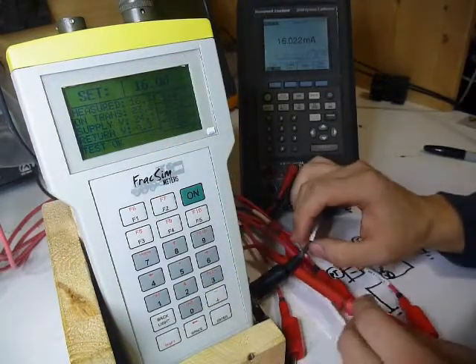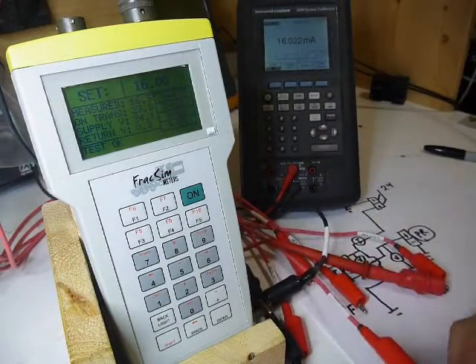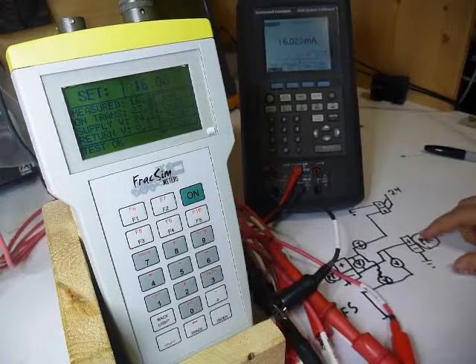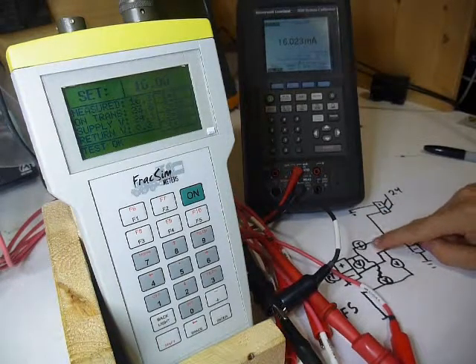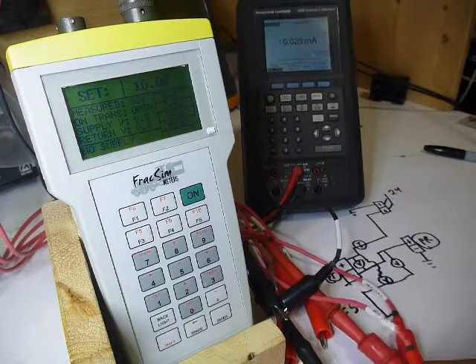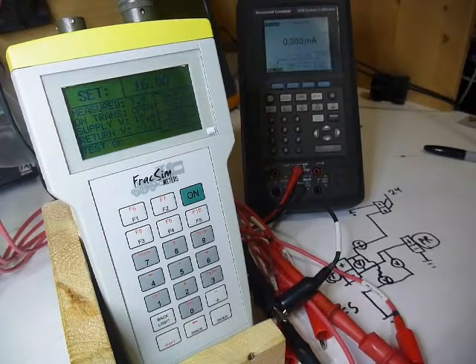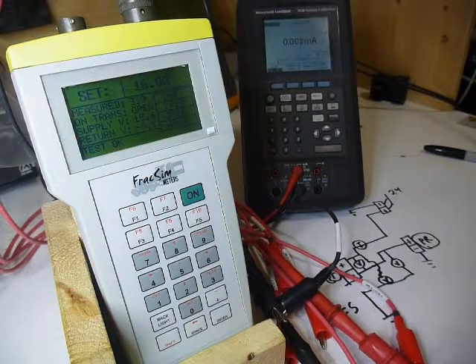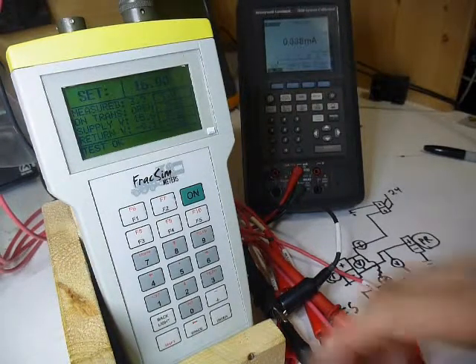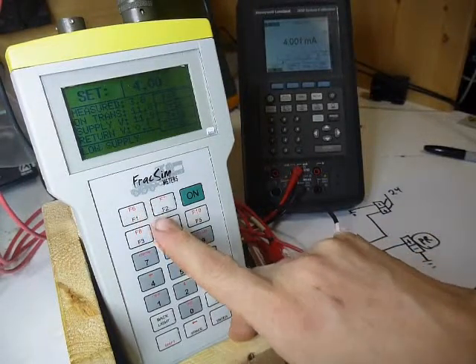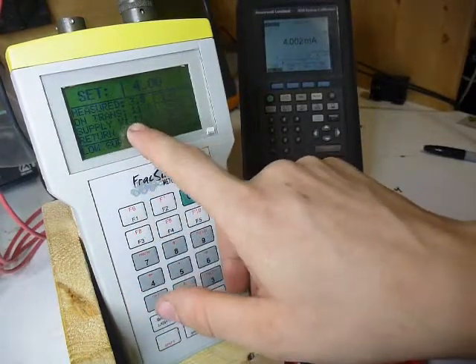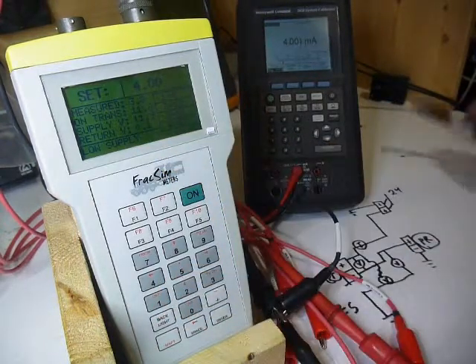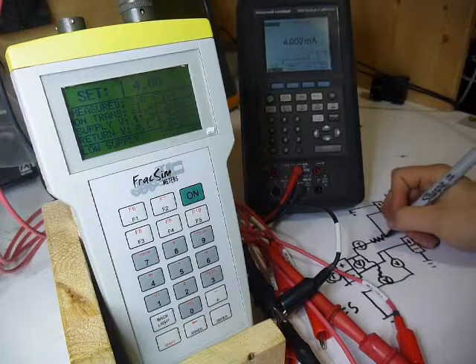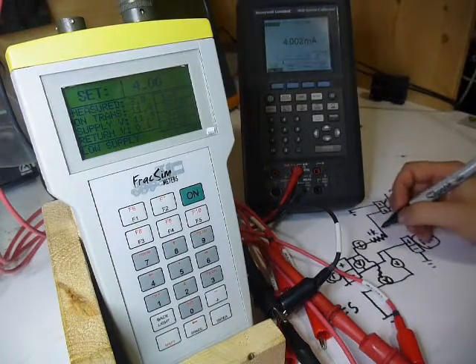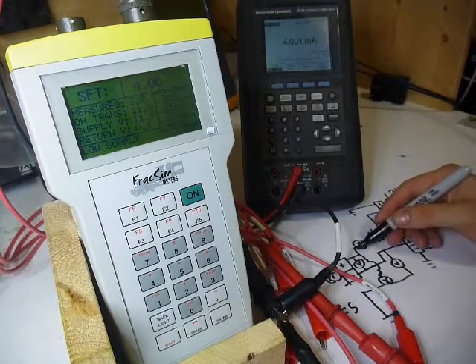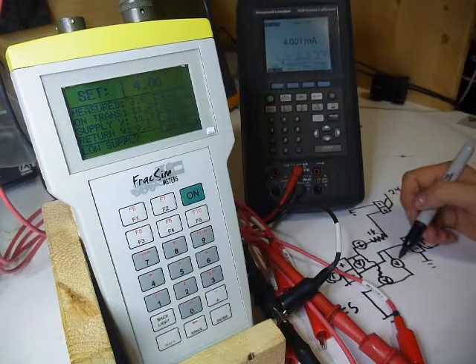But what I'm going to do now, like I said, is put this 1000 ohm resistor in the supply side, which is the 24 volts. If you were to look at this circuit, it'd be the 24 volts if I were to put a resistor in here somewhere. So I'm going to go ahead and do that. So you see now the supply voltage has dropped right down. Our supply voltage is now 11 volts. And the reason that's happening is you've got a resistor in here, way too high, 1k ohm. You're getting a big voltage drop right here. So now these voltage readings here are obviously going to be low.